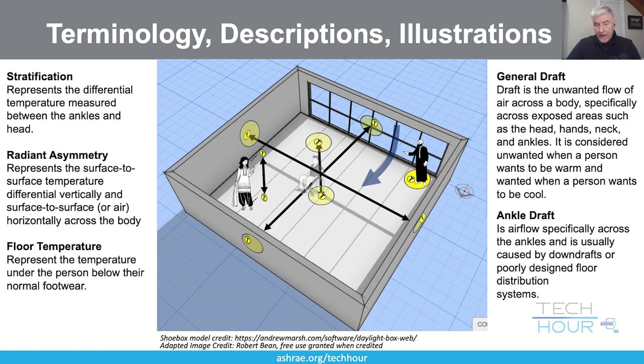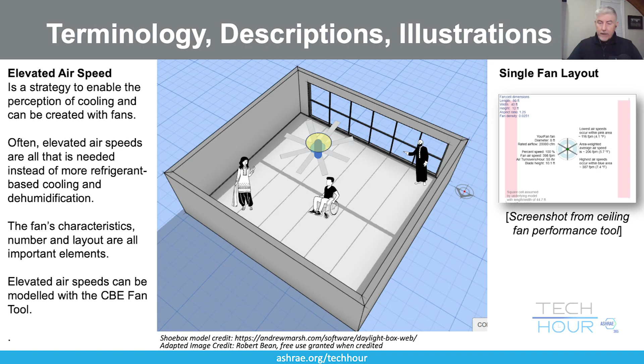One of the key areas of interest for ASHRAE Standard 55, our technical committee SSPC 55, has to do with elevated airspeeds. We know that when we can elevate the airspeed with, for example, ceiling fans, we can achieve an equivalent cooling effect through this fan. We're not actually cooling the space, but the occupant's perception of the space is cooler. And it's much more energy efficient to use the ceiling fan solution as opposed to adding more mechanical cooling. So we would encourage those looking for compliance with ASHRAE Standard 55, rather than defaulting to mechanical solutions for cooling, to try to incorporate elevated airspeeds in your assessments.